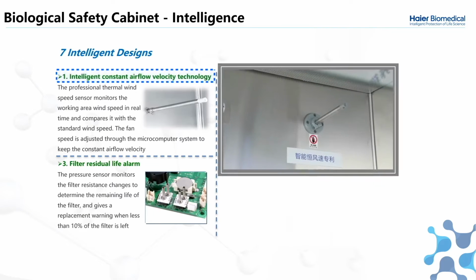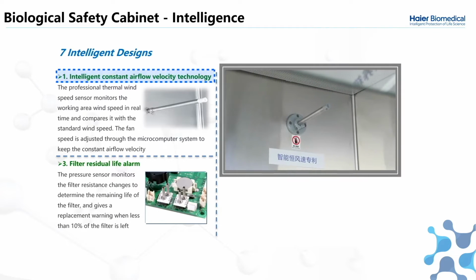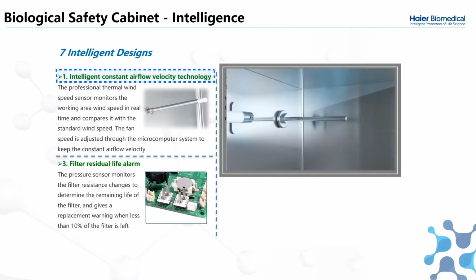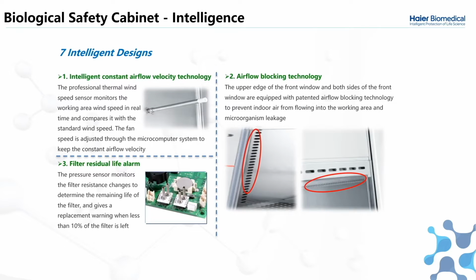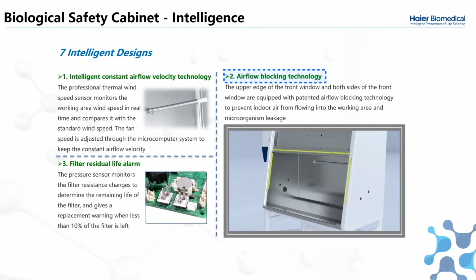In a bit more detail, you have the intelligent constant airflow velocity technology, which allows you to actively monitor the airflow inside the cabinet. There's also air blocking technology, which prevents indoor air from flowing into the working area and affecting the laminar flow, and prevents any leak of air from inside the cabinet.